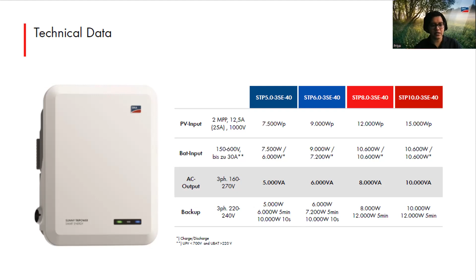And you can see the AC output of the inverter is according to its rated capacity. So 5 kilowatt, 6, 8 or 10. And at backup, you can get continuous backup of the full power of 5 kilowatt. If required, some overloading is also possible in case of backup when you don't have grid support. If you have loads which require very high starting current, even for the 5 kilowatt inverter, you can get as high as 10 kilowatt for 10 seconds. So whatever loads you have, you will be able to use them. All the residential or small commercial application loads would be supported by this system.